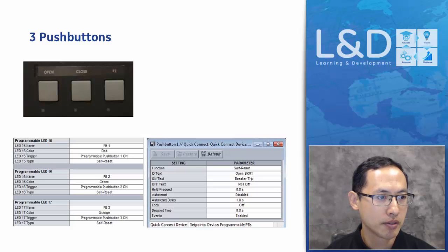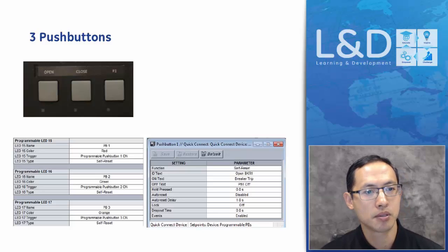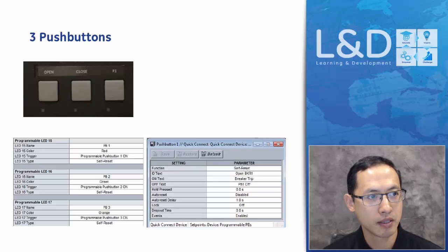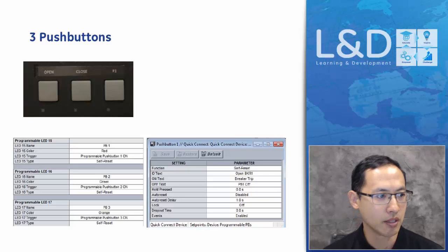And the push buttons can be used to send a command. Typically, by default, push button 1 is set as trip, push button 2 is set to close, and the third button, F3, is unprogrammed. So this can be used to send an open or close command to the breaker, and once a button is pressed, the corresponding flex operand will be asserted.